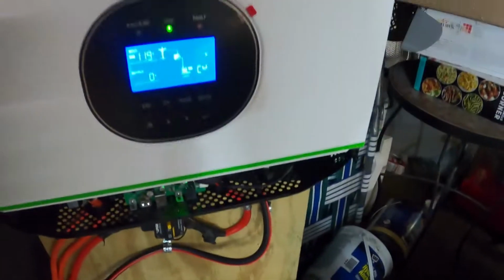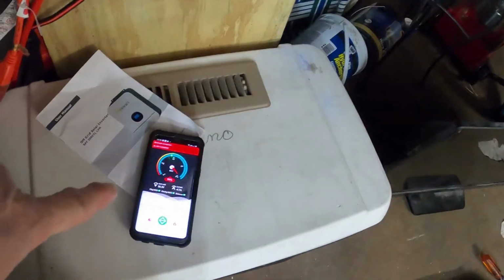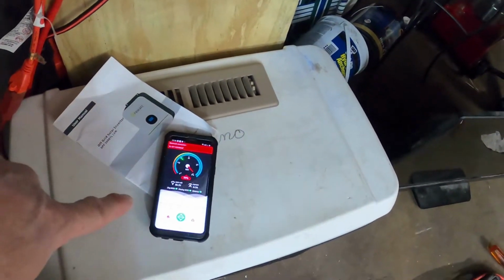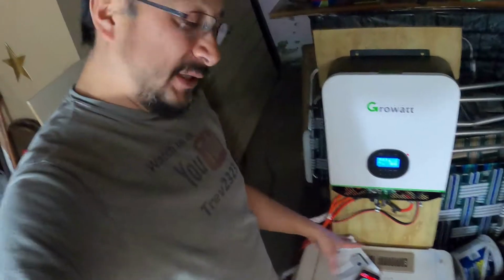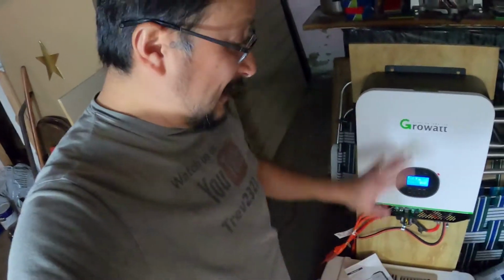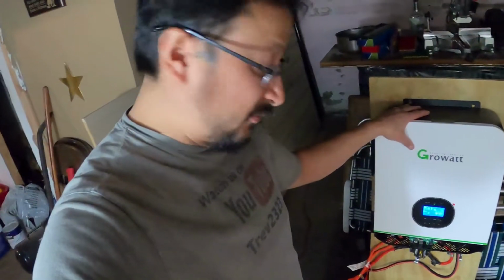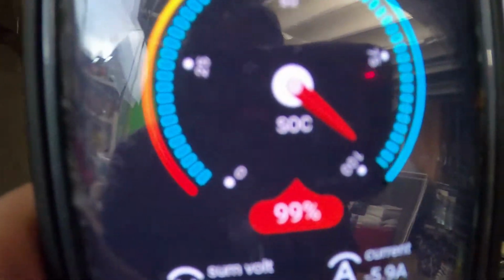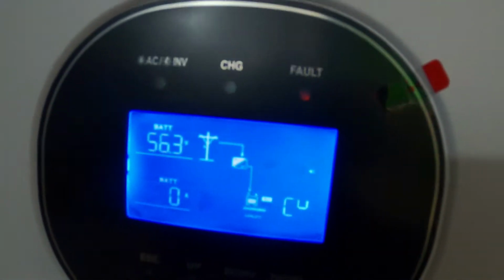I'm up to 56.3 volts. I'm trying to see what's going to happen when it gets to 56.4, if it'll finally go to 100%. Like I said, the Daly BMS high cutoff is 59, but this one's set at 56.4, so I'll keep you posted, and I'm going to get that TV plugged in today. The battery is at 56.3, and it's reading exactly what it is on the Daly BMS, so we'll see if that shuts off.